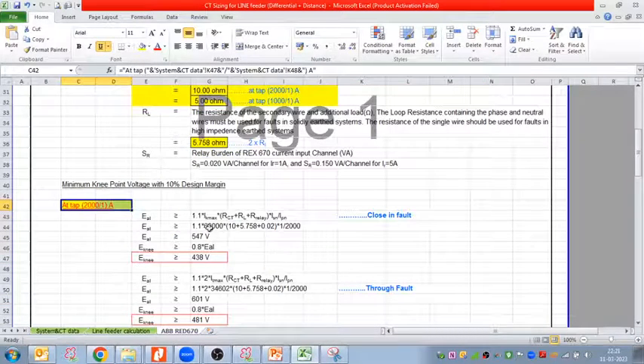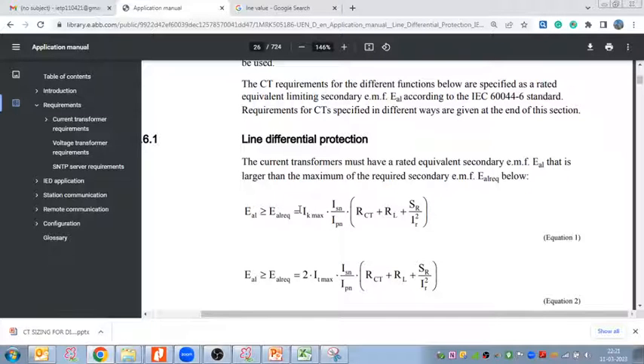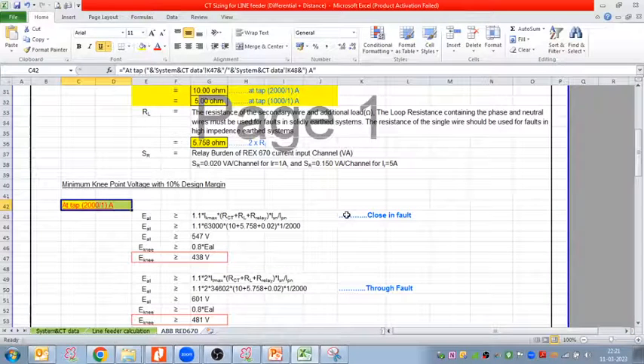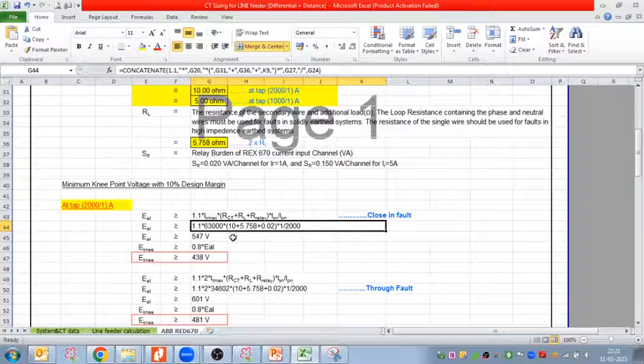So IK max here is my fault current. So fault 63 kiloampere multiplied by 1 divided by 2000, multiplied by all in the bracket. So 63 into RCT, which is my 10 ohm.